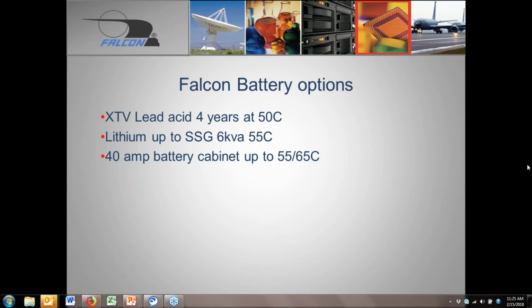One more question: is there some type of communications network card that can be installed? Not specifically to the batteries. There's no battery management system in the UPS structure. The overall operation remains the same as with lead acid. So you still have the option of having SNMP communication to the UPS. However, the parameters specific to the battery remain the same as with lead acid.